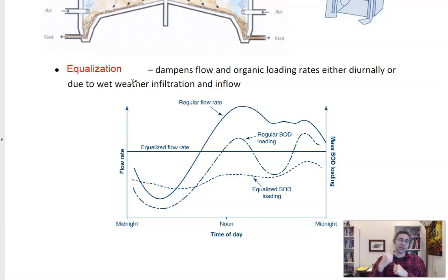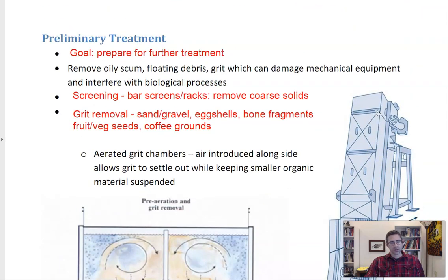there's ways they can start recirculating wastewater within the plant in order to accommodate higher flow rates, so all the tanks fill up a little bit more. You have more coming in, less going out, and you just treat the water maybe several times to achieve your treatment objective. So there's different ways that is handled at different plants, and so not all have an actual equalization tank, either inline or offline, that they use. So that's essentially all of preliminary treatment, and then next lecture is going to talk about primary treatment, which is the next step in the process.